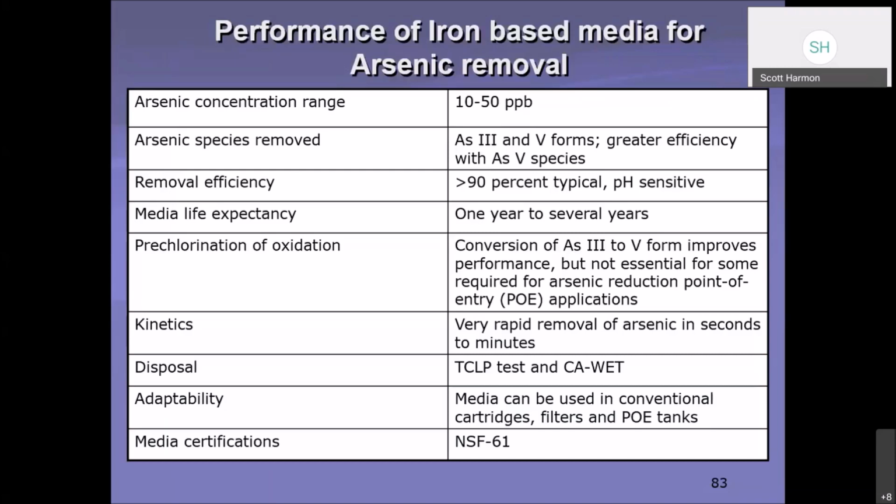Media life expectancy, I like that they said 1 year to several years. So, yeah, I guess that's true. Pre-chlorination or oxidation, conversion of the arsenic 3 to 5, improves performance, but is not essential for some, required for arsenic reduction at a point of entry application. So, again, if you went to a combination of point of entry devices or point of use devices, you may not have to do the full conversion over to the less mobile form of arsenic.